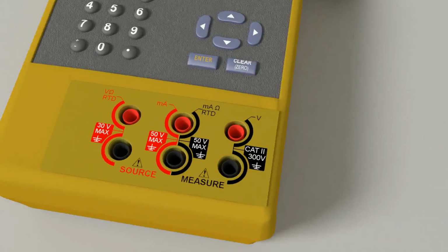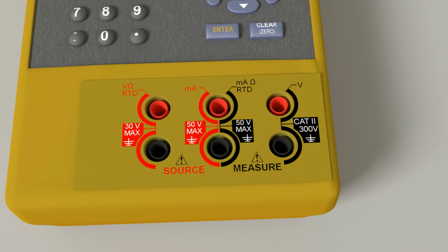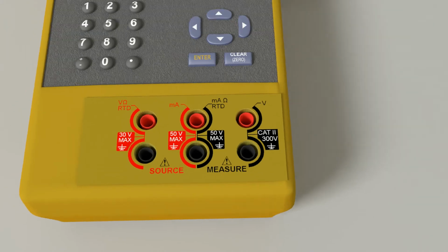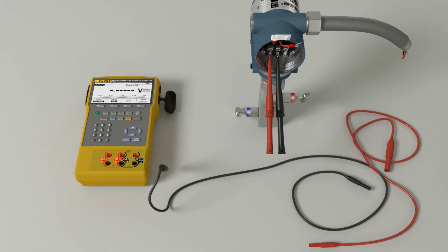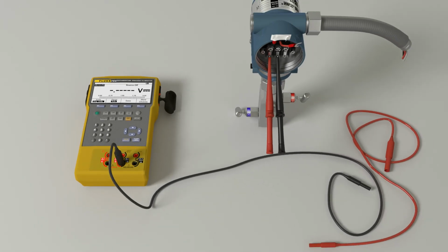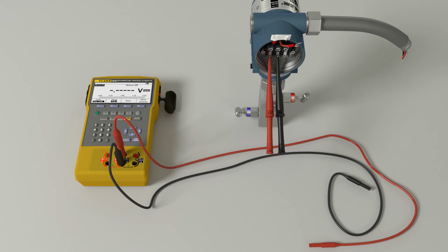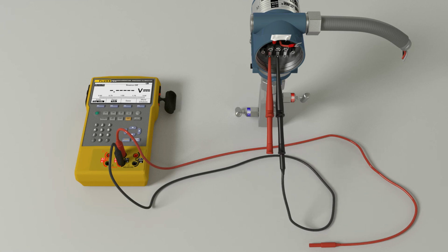Looking at the Fluke meter, you will see there are 6 ports. Place one side of the black lead in the middle black port on the 754. Then place one side of the red lead into the middle red port of the 754. Now connect the other side of the black lead into the connector that is attached to the transmitter. Then the red lead to the red connector.